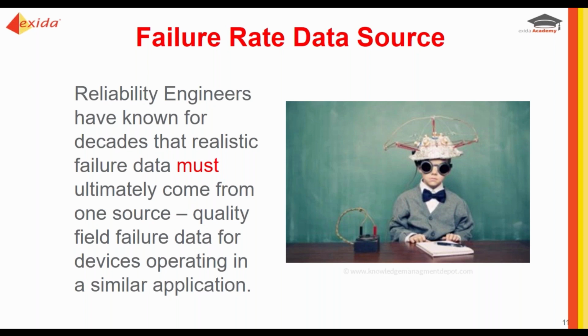If you are a nuclear power plant, do not take the failure rates or the field failure data from an offshore reliability company from the North Sea. That is not going to be the same application. It's not going to be the same operating environment.